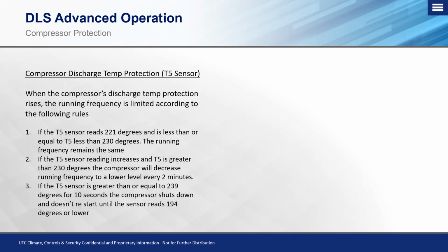If that T5 sensor reads greater than or equal to 239 degrees for 10 seconds or longer, the compressor will shut down and does not restart until the sensor reads 194 degrees or lower. And essentially this is to protect that oil, because at 239 degrees and above for long periods of time, we can start to break down that oil or carbonize it. And essentially we're going to contaminate the system if we get that oil too hot. And of course, the system is going to be pretty much a total failure once that happens.